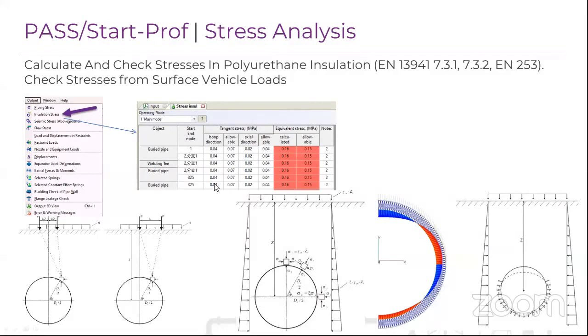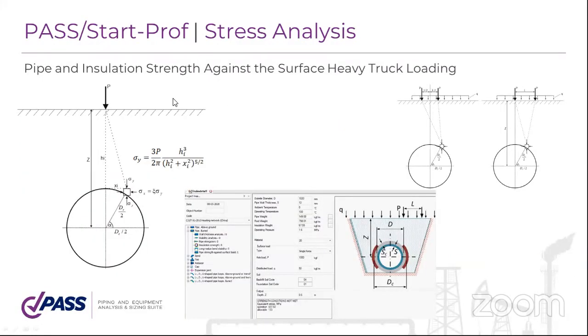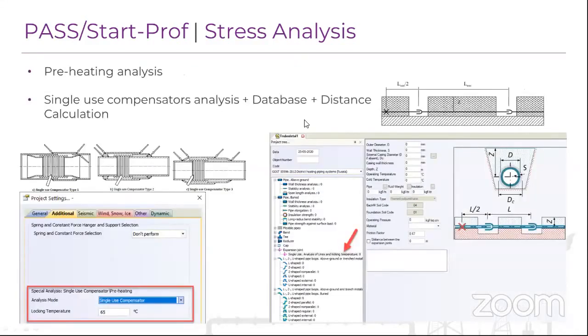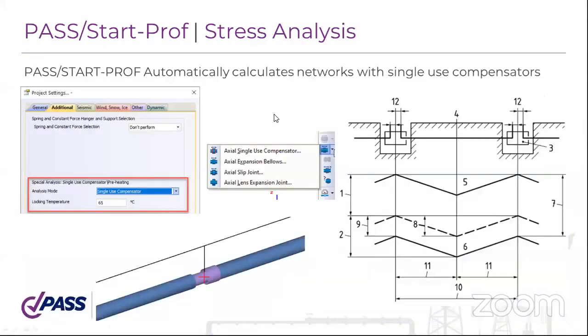StarProf can analyze the stresses in polyurethane foam insulation. The friction forces acting on the insulation must be passed from the insulation to the steel pipe, so the adhesion must be very strong. StarProf checks the insulation stresses according to EN 253 code automatically, combining results from the cross-section nonlinear finite element model and the beam element pipeline model to calculate equivalent stresses and tangential stresses in the hoop and axial directions. StarProf can also analyze insulation and pipe under external loads on the ground surface, such as from heavy trucks above the pipe. It can also take into account preheating and the single-use compensator, and can calculate the distance between single-use compensators.